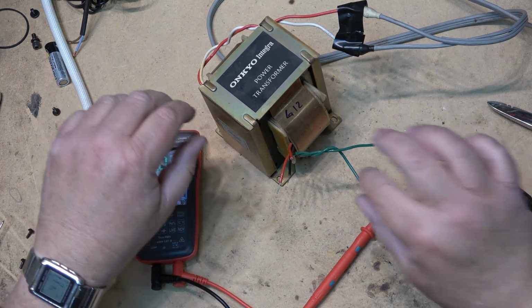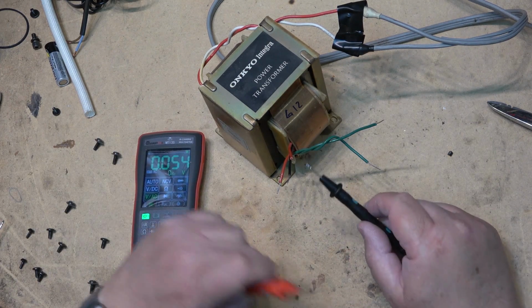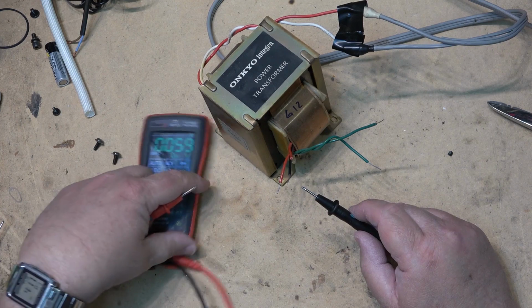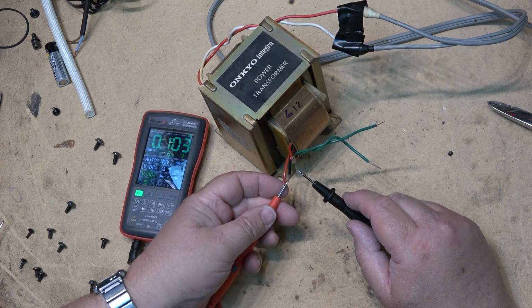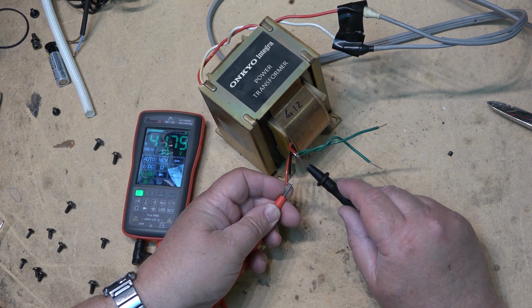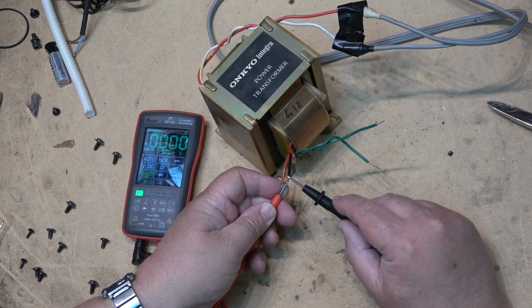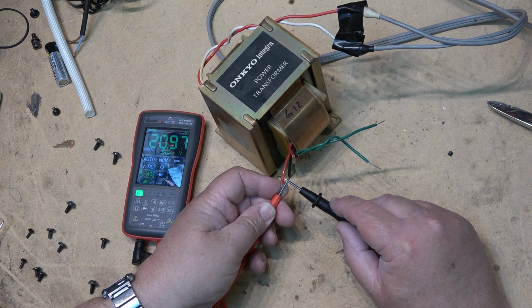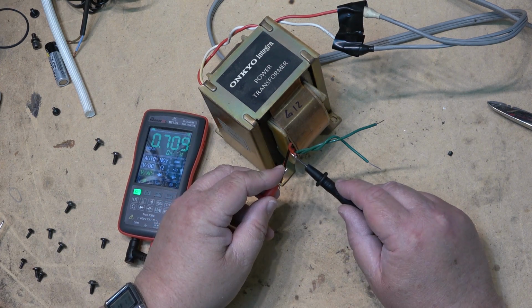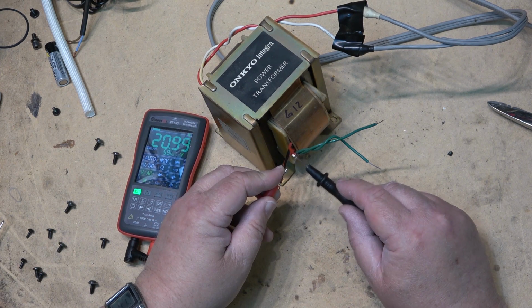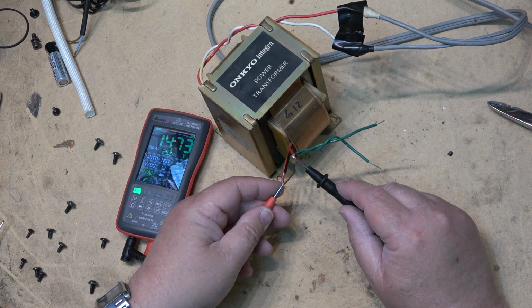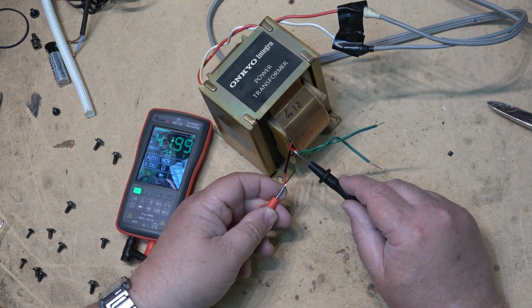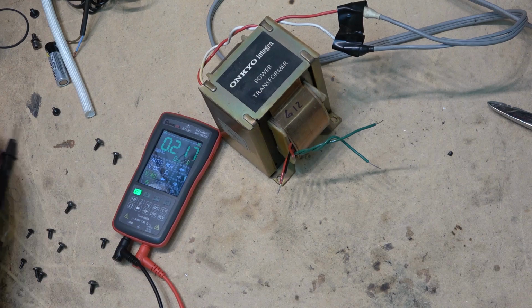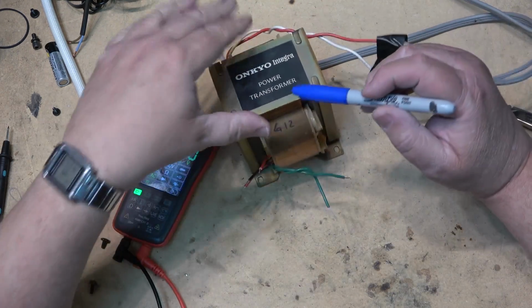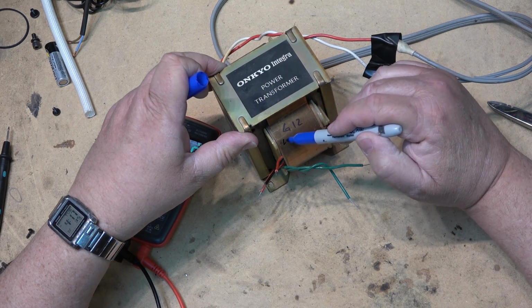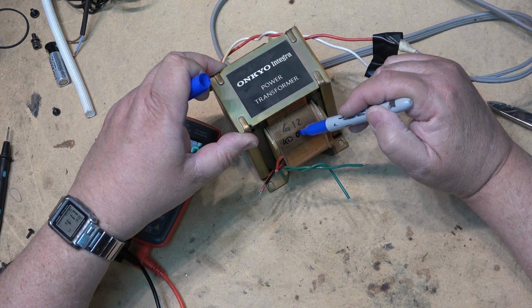The other winding, these are isolated from this other one, at least they should be. This other one has a total of 41 volts, so in other words, 82. So it should be 20 volts per winding. So it should be 40 for center tap and 80 across. That's a 40, 0, 40.